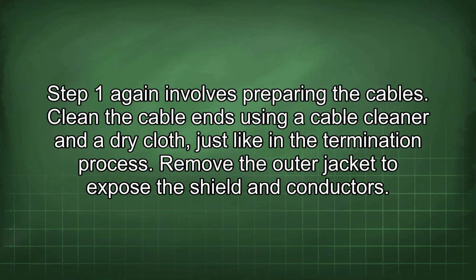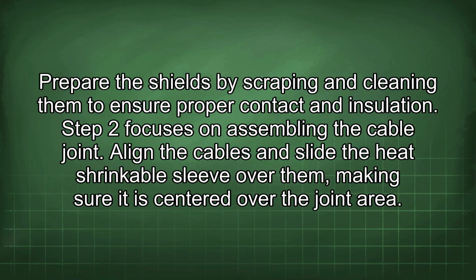Step 1 again involves preparing the cables. Clean the cable ends using a cable cleaner and a dry cloth, just like in the termination process. Remove the outer jacket to expose the shield and conductors. Prepare the shields by scraping and cleaning them to ensure proper contact and insulation.